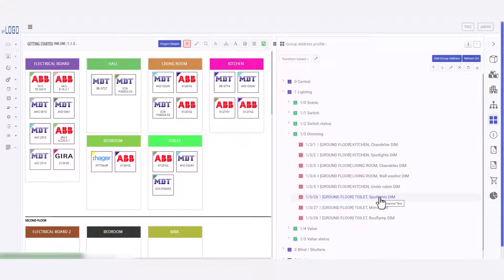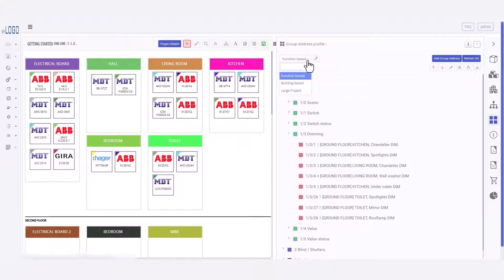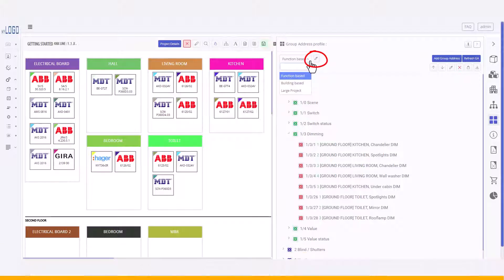Here we can see the group addresses for the device I just configured. The KNX Tool includes three predefined group address profiles that determine what the GA structure will look like. You can fully customize these profiles to fit your specific needs in the project settings.